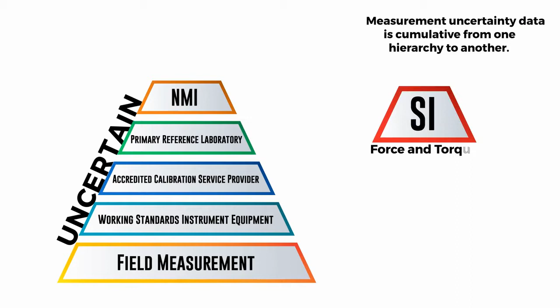Let's first define measurement traceability. That measurement traces back to the International System of Units, SI. For force and torque, these SI units are time, length, and mass. The pyramid starts with SI at the top, then National Measurement Institute, NMI, like NIST. If NIST did the calibration of the force weights, then the next tier would be a primary reference laboratory, like Morehouse. Morehouse performs calibrations on load cells for the lower tiers, accredited calibration suppliers, followed by working standards who in turn calibrate field equipment.